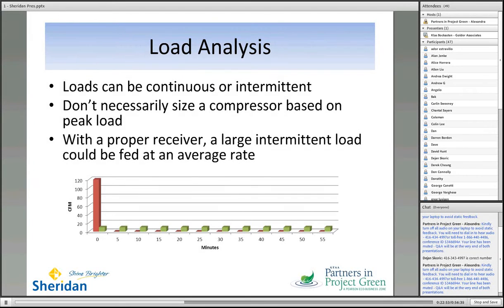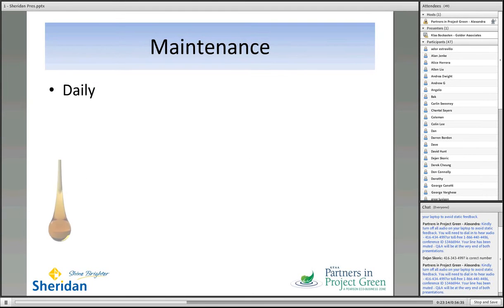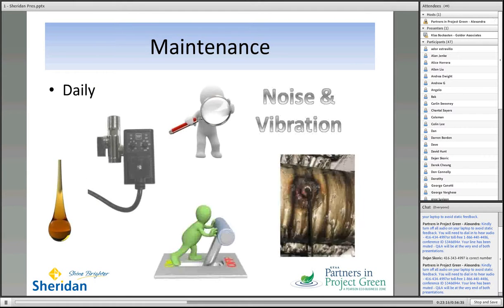Then on a periodic maintenance basis, be sure to take a look at those pressure relief valves. Make sure they're actually functioning so that when you need them, they'll function. Clean the cooling surfaces on your intercooler or aftercooler compressor. Look for leaks on your compressor. Check your system for leaks periodically. So we've seen the cost of that. Inspect and change lubricant. Look at your air intake filters and check your V-belts for tightening.